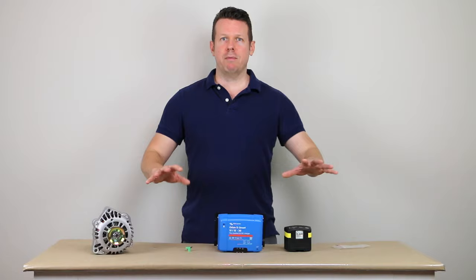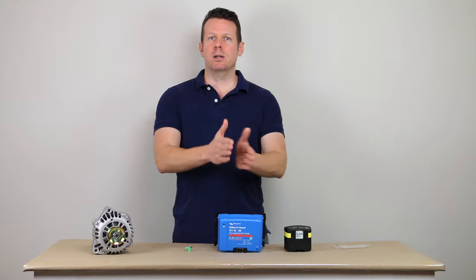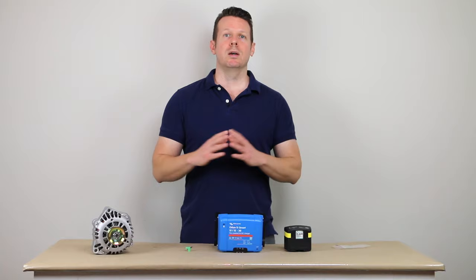And you want to make sure that you go back after you've assembled everything. You can assemble it loose. You don't have to go crazy trying to tighten everything as you build it. But once you build it, go back and check systematically, check each bolt, check each connection, turn these screw terminals, make sure they're still tight, things like that.